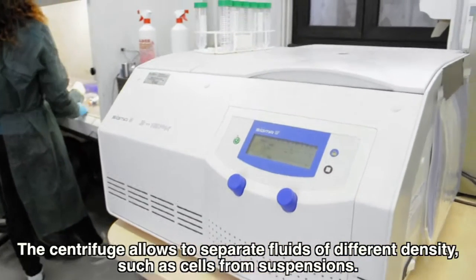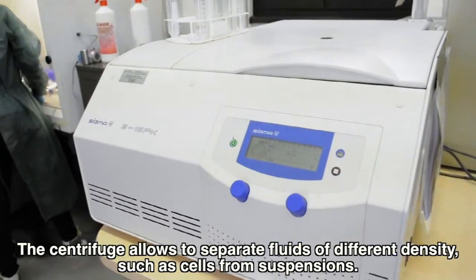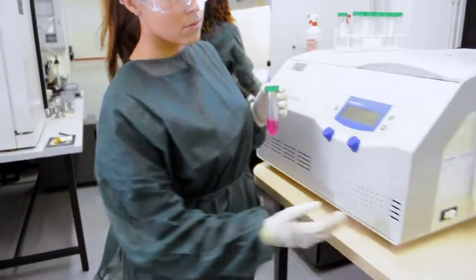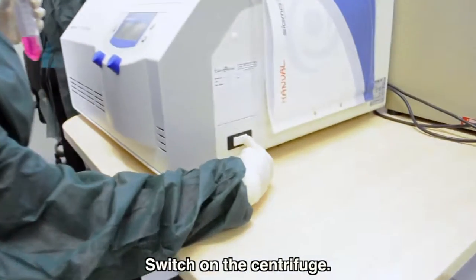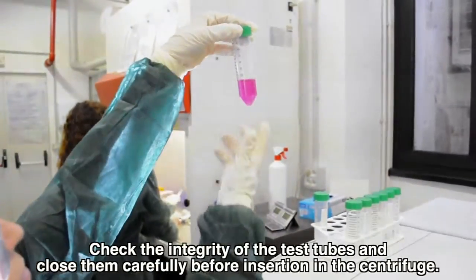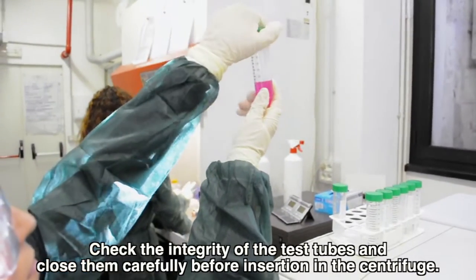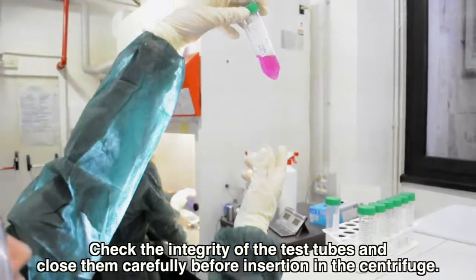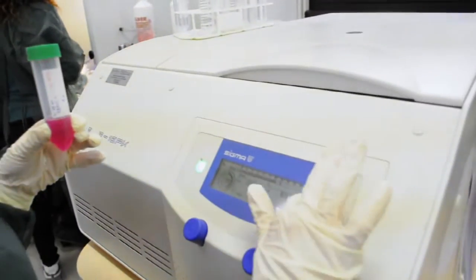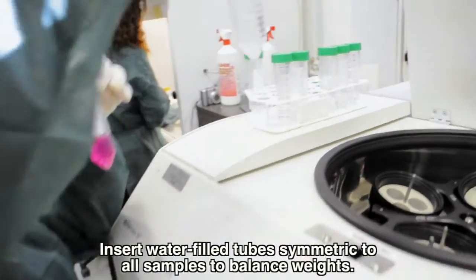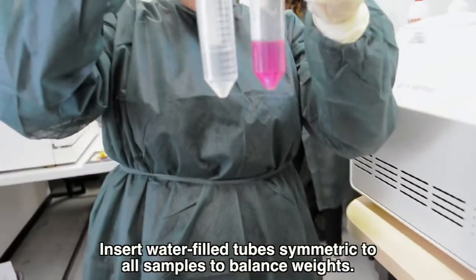The centrifuge allows to separate fluids of different density such as cells from suspension. Switch on the centrifuge. Check the integrity of the test tube and close them carefully before insertion in the centrifuge. Insert water-filled tubes symmetric to all sample to balance weights.